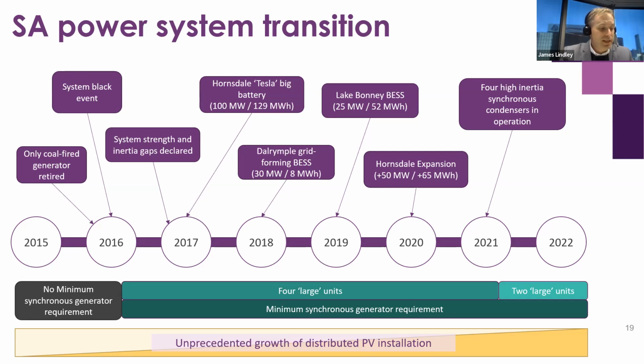Following the Tesla Big Battery, we had a number of other batteries installed. The Dalrymple battery in 2018, which is a grid forming battery, although a relatively small one, only 8 megawatt hours. We also had the Lake Bonney battery installed. In 2020, we had the expansion of the Hornsdale battery, another 50 megawatts and 65 megawatt hours. Then in 2021, we had the commissioning and construction of the 4 high inertia synchronous condensers.